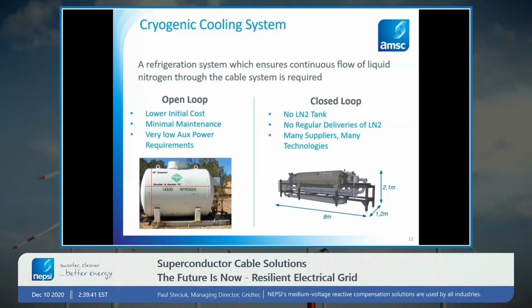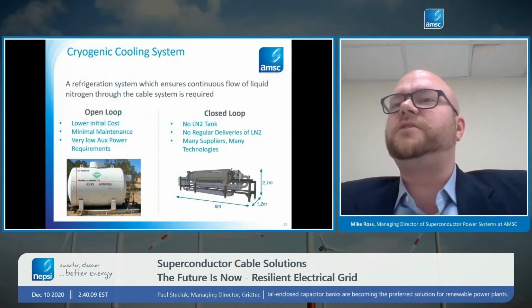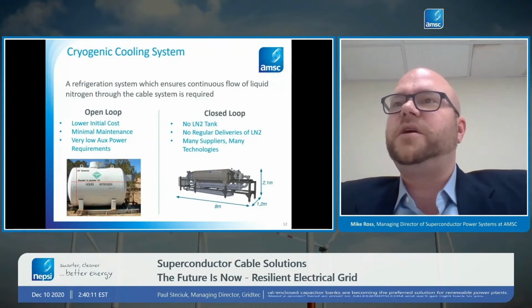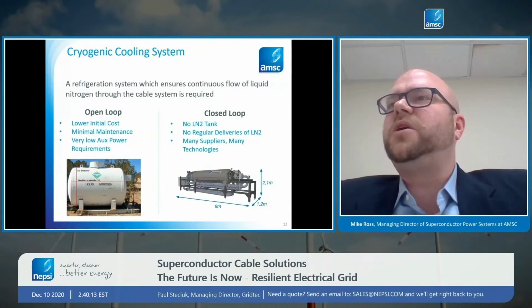The attractiveness of this approach is that it's very low initial cost. There's very little equipment. There's very little maintenance. Aside from a pump, you really have no moving parts, and you're not using very much electricity to cool the cable. The downside of this approach is that you need to find a place to install that liquid nitrogen tank, and you need to fill it periodically. So for urban utilities that have very tight substations and don't have a lot of space, this isn't attractive. So that's when we go to what we call a closed loop system.